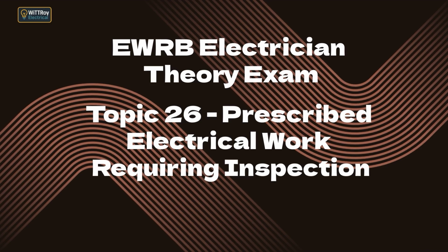Summary. Some installation work must be inspected before connection. Only a registered electrical inspector can do this inspection. Regulation 70 lists high-risk prescribed electrical work requiring inspection. Work involving mains or hazardous areas requires inspection. Regulation 72 requires inspectors to consider companion standards, not just AS/NZS 3000. Installation cannot be connected to supply until the inspection is complete.